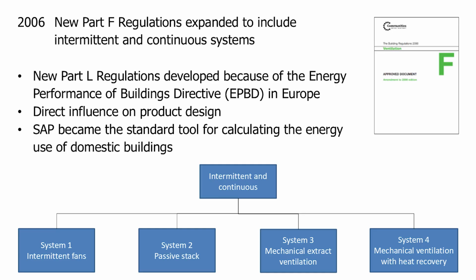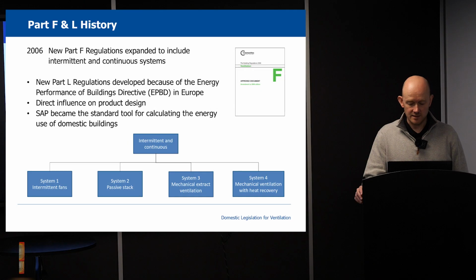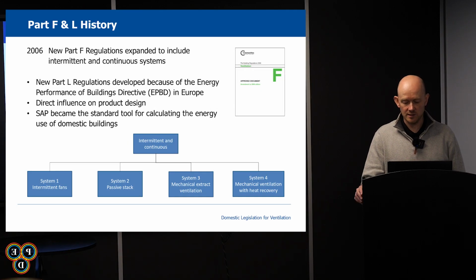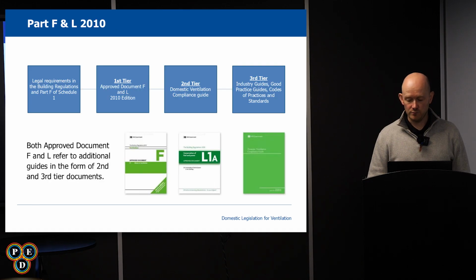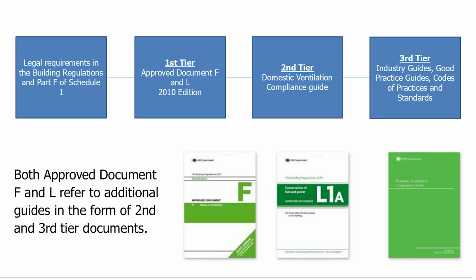Part L, conservation of fuel and power, was also introduced and gave rise to the fan system having a minimum specific fan power. Starting the drive to energy efficient systems, Part L was split into L1A for new builds and L2A for refurbishments. In 2010, Part F was updated to include reference to the Domestic Ventilation Compliance Guide, which introduced the requirement for commissioning of systems and compliance documentation, creating a more stringent process for ventilation.